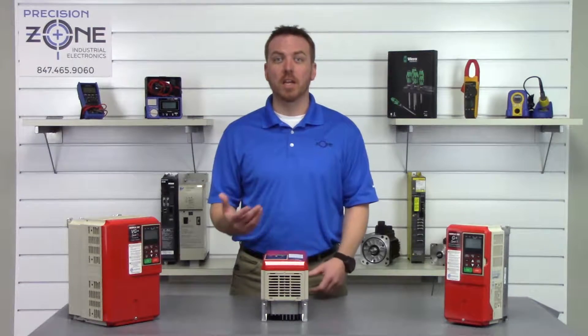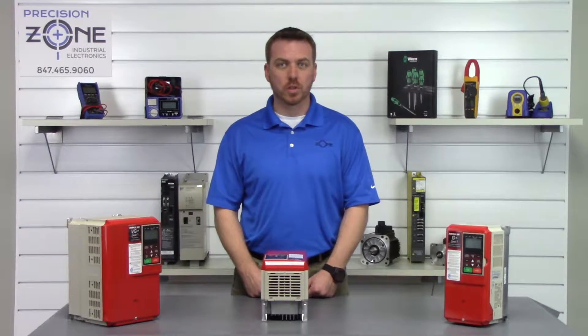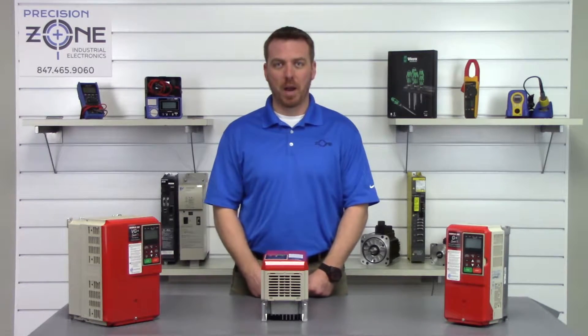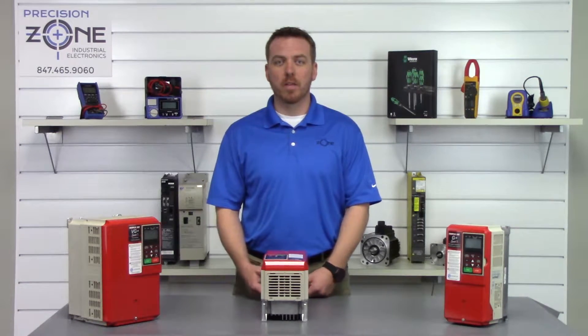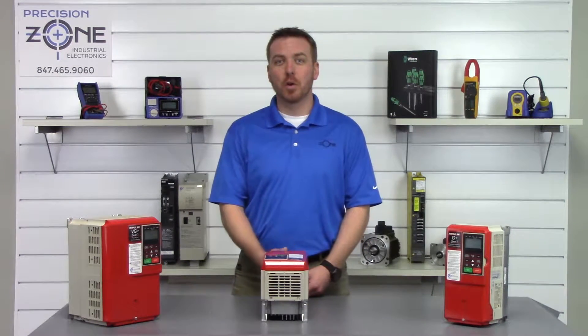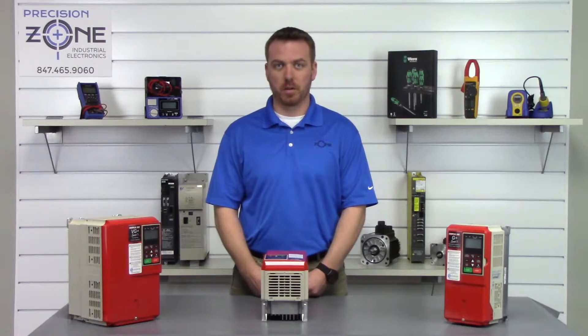OU is an overvoltage and UU is an undervoltage alarm, and this could be a problem with your incoming power. You'll want to verify that the incoming power is within the correct range and that it's balanced on all three phases with a true RMS meter.